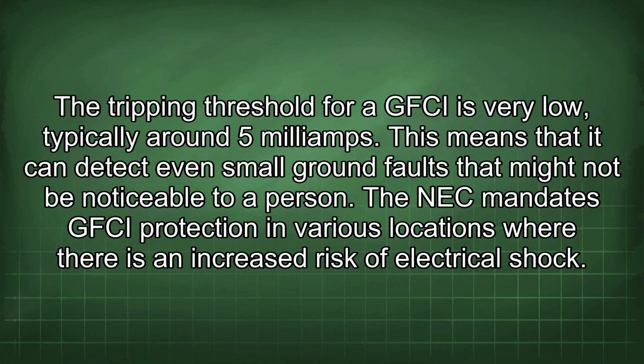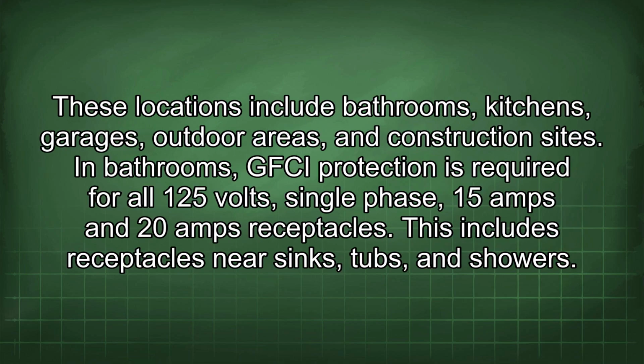The tripping threshold for a GFCI is very low, typically around 5 mA. This means that it can detect even small ground faults that might not be noticeable to a person. The NEC mandates GFCI protection in various locations where there is an increased risk of electrical shock. These locations include bathrooms, kitchens, garages, outdoor areas, and construction sites.